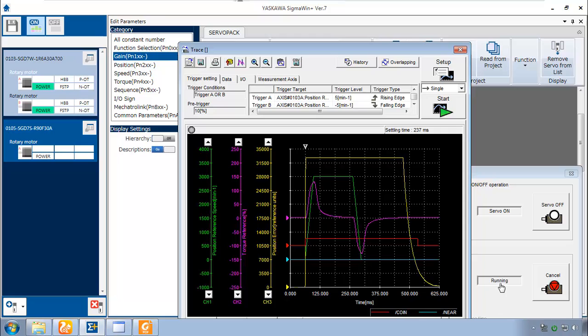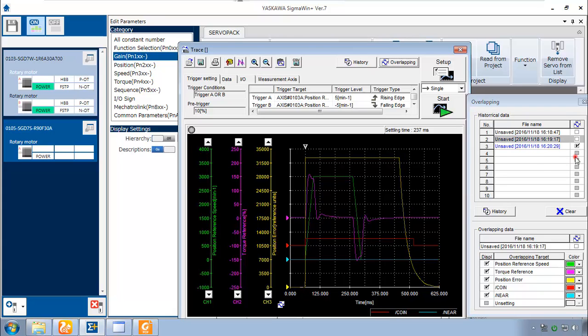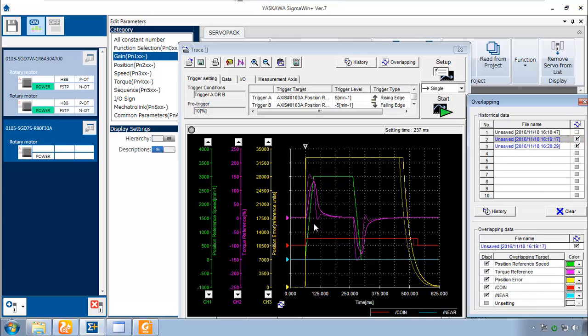What I'm going to do for comparison is to click this overlapping button. And we can compare the current unsaved graph with what we have right now. This was our response right now with a little 50% feed forward. Simultaneously display what we had previously. You can see it made it more aggressive. The torque got a little higher. Looks like our settling time came down a little bit.